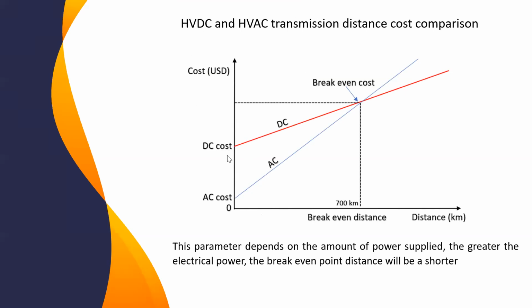But for DC, we have a converter station, so the initial cost is quite expensive. However, because DC needs fewer conductors, a smaller tower, and a smaller right of way, by rule of thumb, for 700 kilometers of overhead line, the break-even cost between AC and DC can be reached. For cable, it's about 40 to 50 kilometers. But this is once again a rule of thumb, it really depends on the power parameter—the more power we transfer, the shorter the distance for break-even cost.